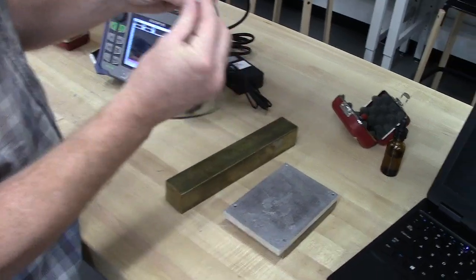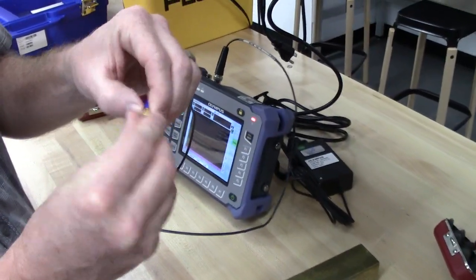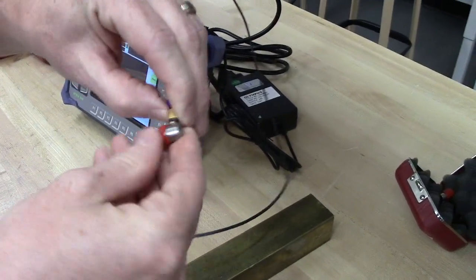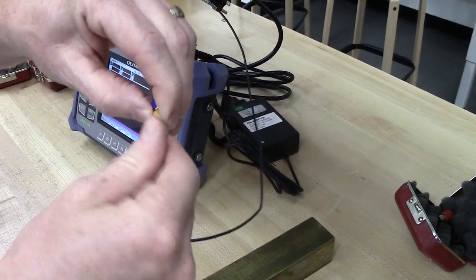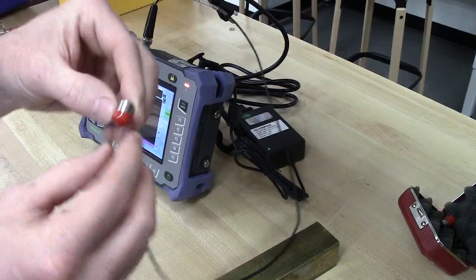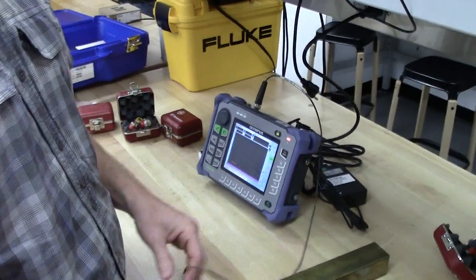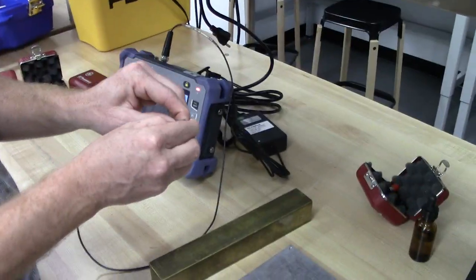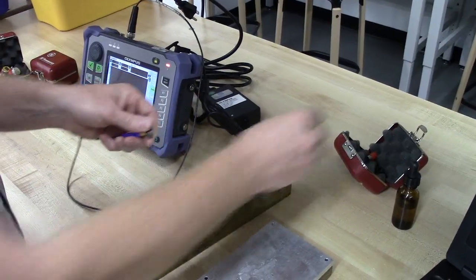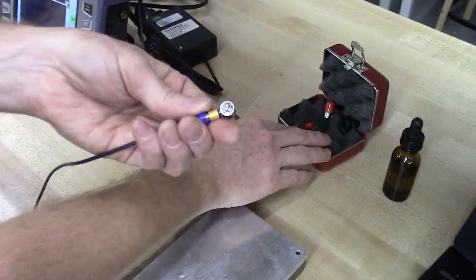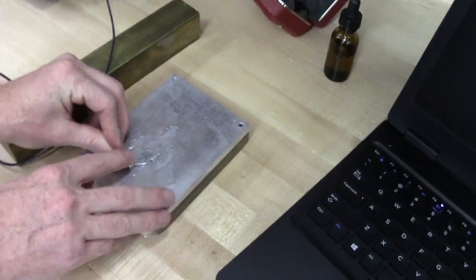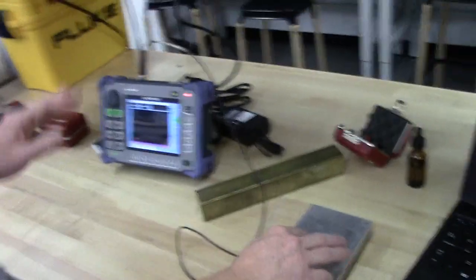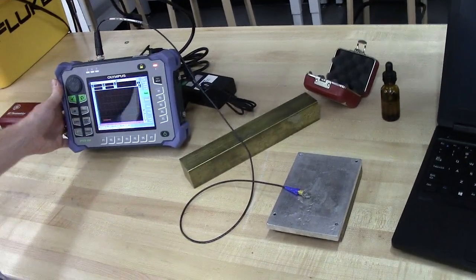Let's get this. We'll screw it on here. So you just get that right lined up on that inner wire and you screw it on. And some students get confused by this. They think that this is what you hang on to and you use this end. But you actually want to remove this plastic cap. And the end that doesn't have any writing on it, that's the end that you want to put here where you're measuring. But we should be pretty good to go for the first part.